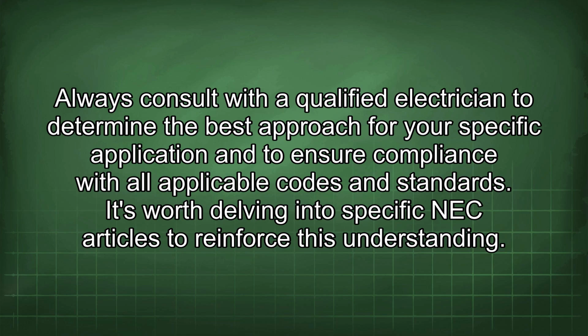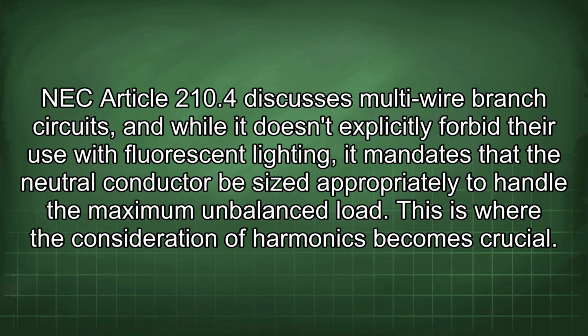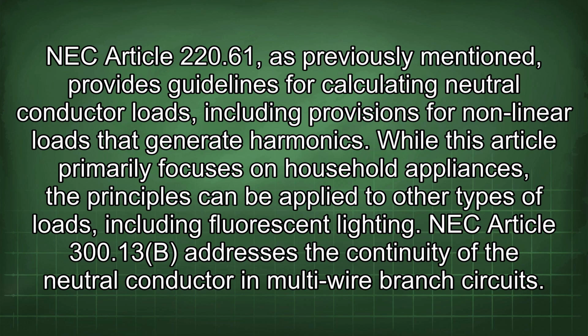It's worth delving into specific NEC articles to reinforce this understanding. NEC Article 210.4 discusses multi-wire branch circuits, and while it doesn't explicitly forbid their use with fluorescent lighting, it mandates that the neutral conductor be sized appropriately to handle the maximum imbalance load. This is where the consideration of harmonics becomes crucial. NEC Article 220.61, as previously mentioned, provides guidelines for calculating neutral conductor loads, including provisions for nonlinear loads that generate harmonics.